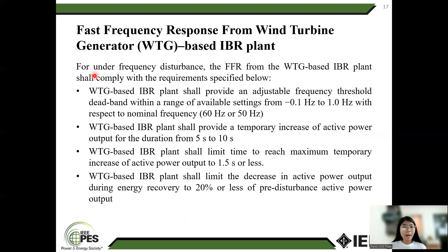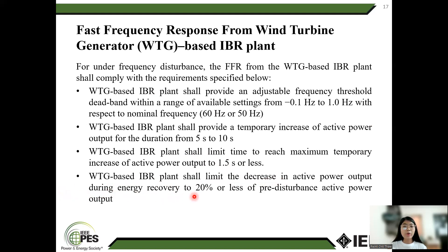The fast frequency response from wind turbines. For under-frequency disturbances, the fast frequency response of wind turbine generator-based IBR plans shall comply with the requirements specified. The wind turbine-based IBR plan shall provide frequency response from -0.1 Hz to 1.0 Hz with respect to nominal frequency of 60 Hz or 50 Hz. The wind turbine-based IBR plan shall provide a temporary increase of active power output for a duration from 5 to 10 seconds, and shall limit response to 1.5 seconds or less. The wind turbine-based IBR plan shall limit the drop in active power output due to energy recovery to 20% or less of pre-disturbance active power output.